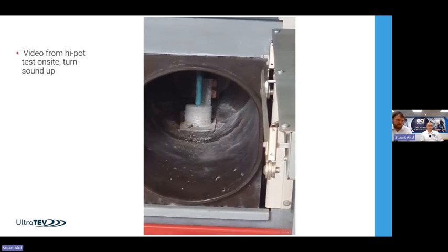So a couple of messages in there. Surface activity in general, stop it happening by keeping things clean and control the humidity. If you have got it going on and you have got high humidity, before you rush out and do anything else, control the humidity, monitor the activity. You can bring that down, buy yourself some time if nothing else. And post flooding, just consider that's something that's becoming more and more topical. We're seeing a lot of questions around these days, unfortunately.